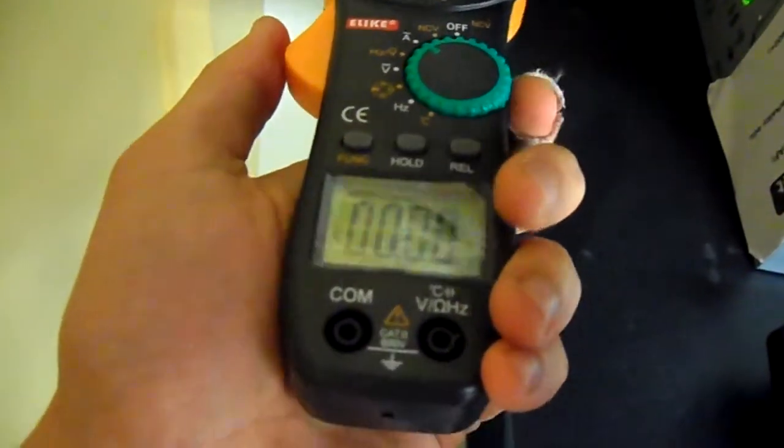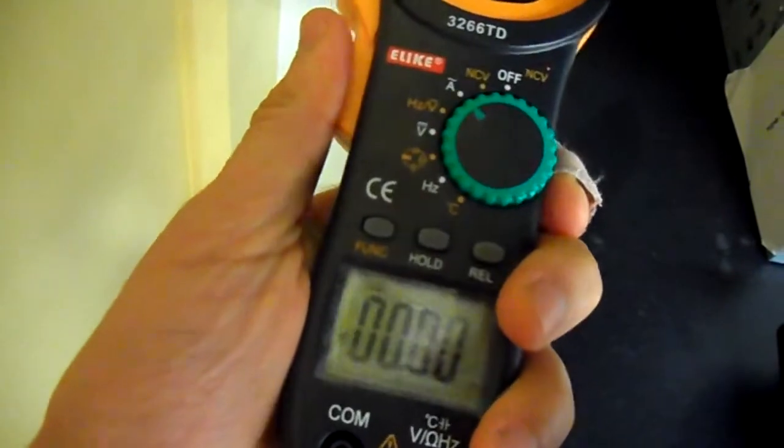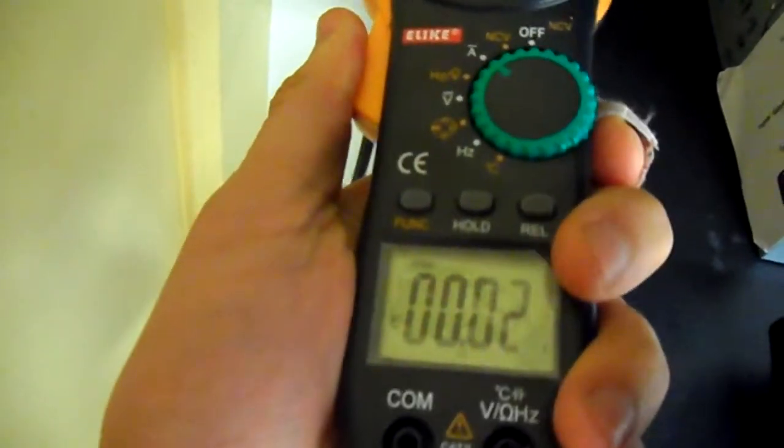And again, if you were to clamp around both, same amplitudes, opposite signs, you see nothing. So if you're measuring with an amp clamp, don't make that mistake.